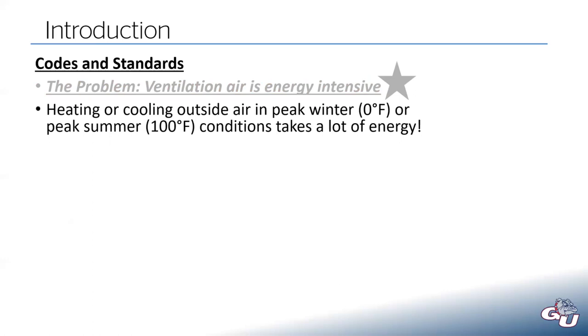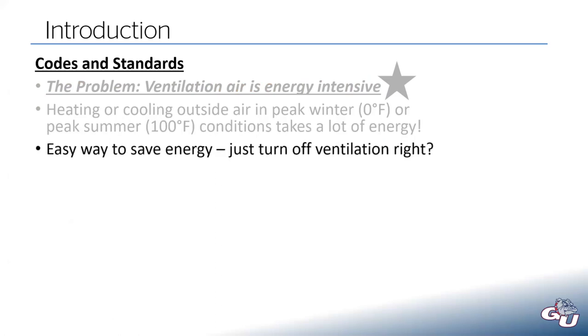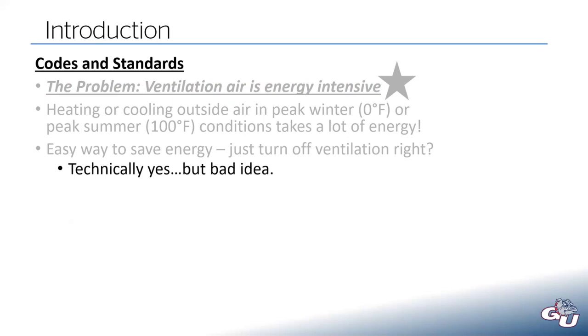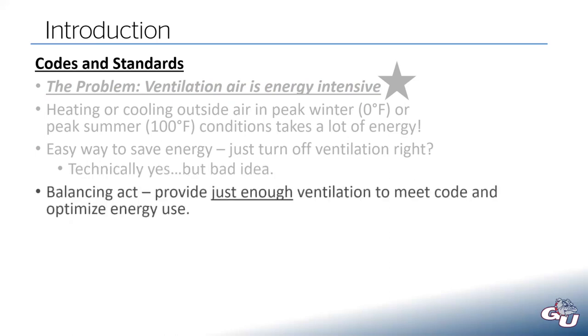And so what I've seen time and time again is, I know an easy way to save energy: just shut off the ventilation. Well, technically, yeah, that will save you quite a bit of energy, but it's not a good idea. So this is an example of one of those balancing acts. We want to save energy, and to save energy, we could turn off the ventilation, but we don't want to compromise something else. So this is the balancing act: provide just enough ventilation to meet code and optimize energy use.